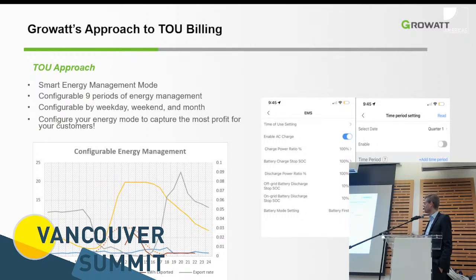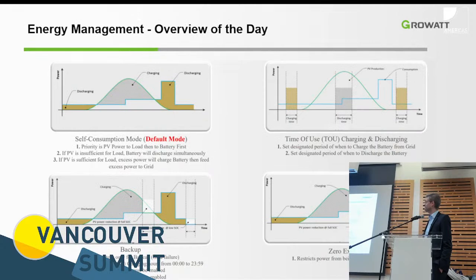And you can configure multiple time frames. That can be on a quarterly basis if you have a seasonal time of use rate. It can be on a weekly basis. It can be on a daily basis if you have a Monday to Friday work week, and then on the weekend you have a different rate structure. And then you specify the times when you have the low rates, when you have the high rates, and the system is automatically calculating when to use the charge and the discharge to optimize for best bang. That's pretty much exactly that.